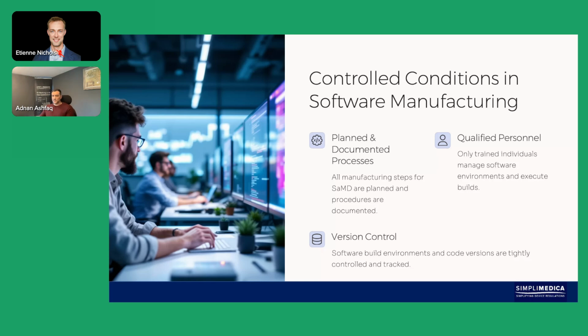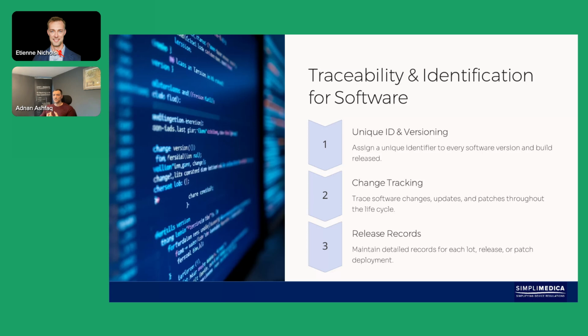Make sure that the processes you're using, whether it's an agile process as opposed to a waterfall process, are discussed in your quality management system. SOUP items, all of those sort of things. You've also got to ensure that you've got ID and versioning, control of software. If you're not validating the software or the SOUP items which are used... SOUP is software of unknown provenance, not the type of soup that we would eat. For those who might be confused, software of unknown provenance is basically off-the-shelf software platforms which you may purchase and use to build your own unique software, which is the medical device software itself. That needs to be validated, and it also needs to be version controlled. There are risks involved in that.